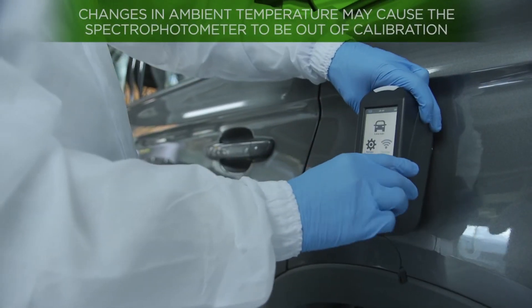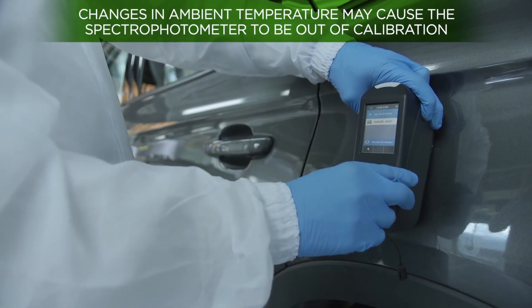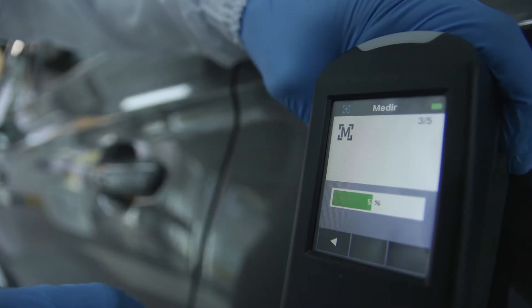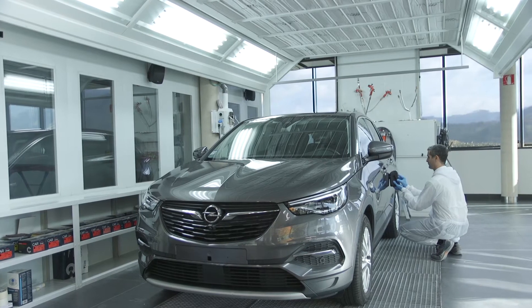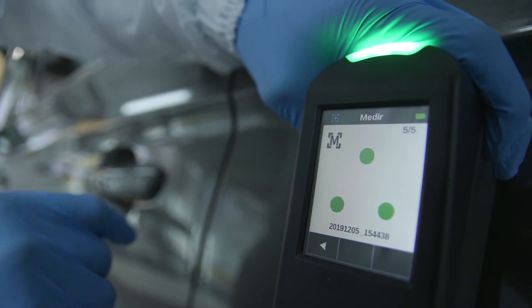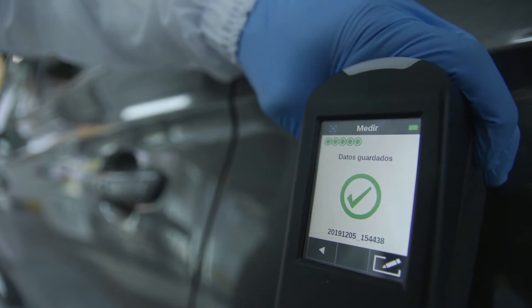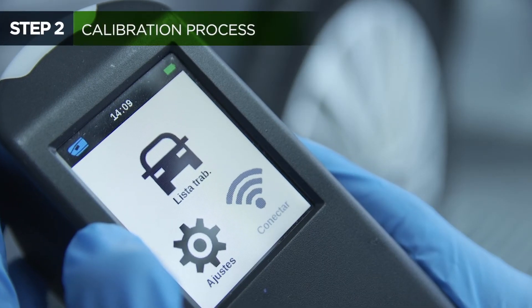Be aware that the spectrophotometer can get out of calibration due to sudden changes in ambient temperature. According to the manufacturer's instructions, the calibration process should be carried out at least every 14 days. Our recommendation is to do it on a daily basis as the time required is minimal in relation to its benefits.